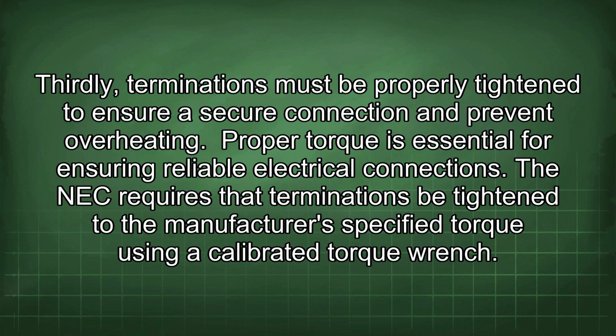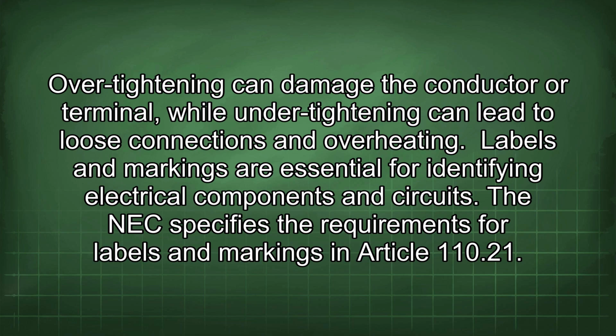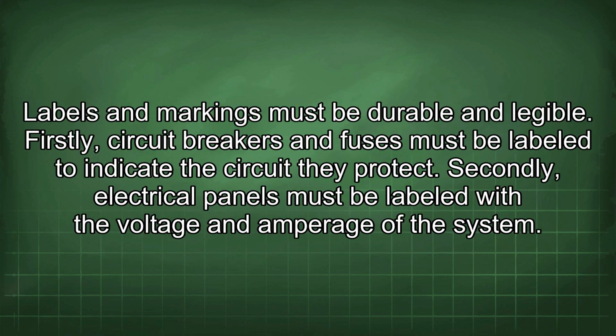The NEC requires that terminations be tightened to the manufacturer's specified torque using a calibrated torque wrench. Over-tightening can damage the conductor or terminal, while under-tightening can lead to loose connections and overheating. Labels and markings are essential for identifying electrical components and circuits. The NEC specifies the requirements for labels and markings in Article 110.21. Labels and markings must be durable and legible.